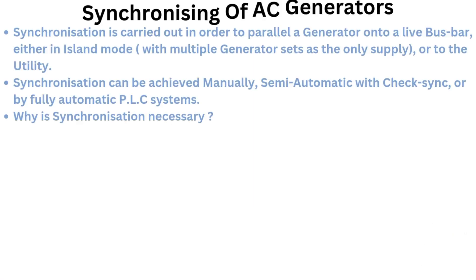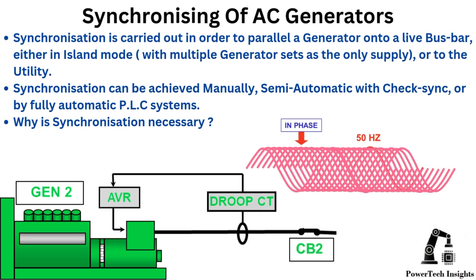Synchronizing of AC generators. Synchronization is carried out in order to parallel a generator onto a live bus bar, either in island mode with multiple generator sets as the only supply, or to the utility. Synchronization can be achieved manually, semi-automatic with check-sync, or by fully automatic PLC systems.